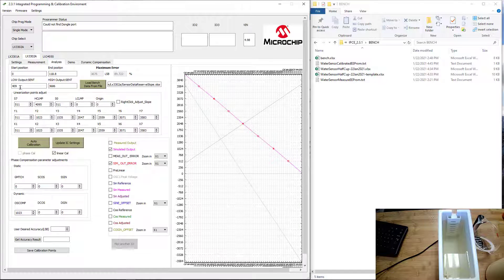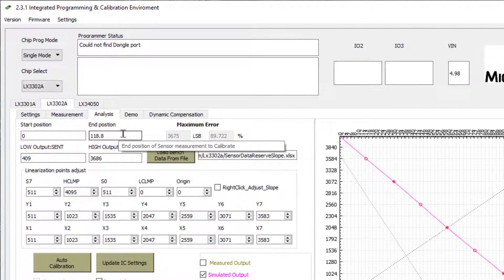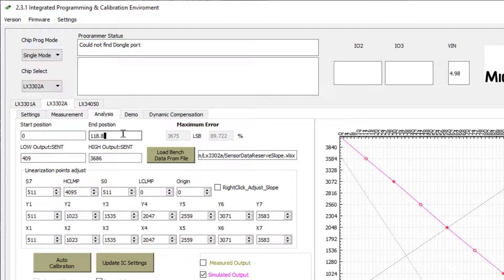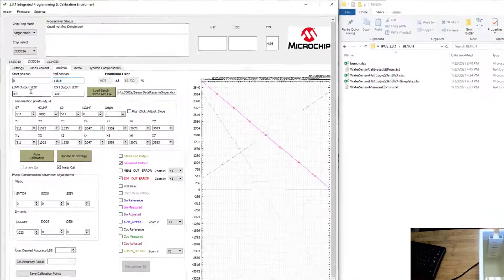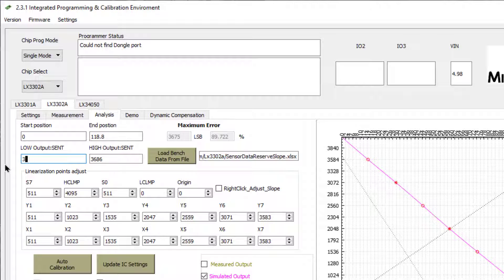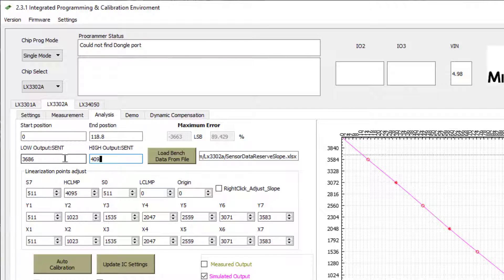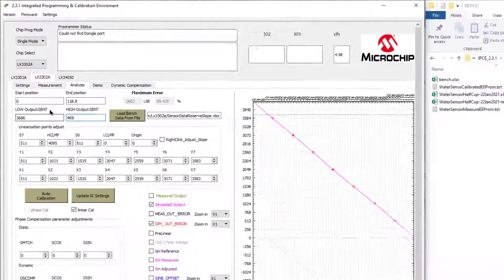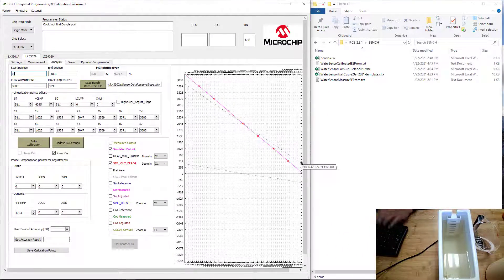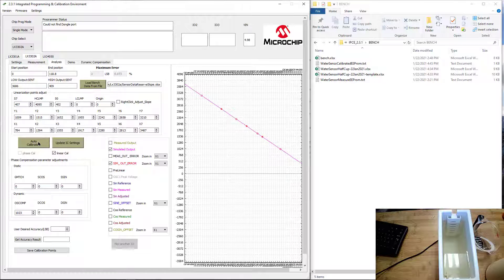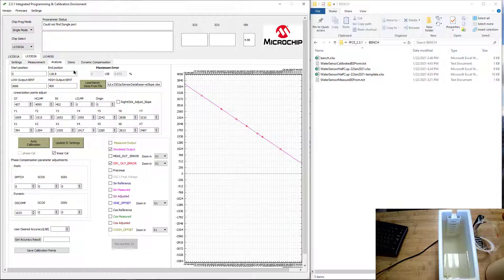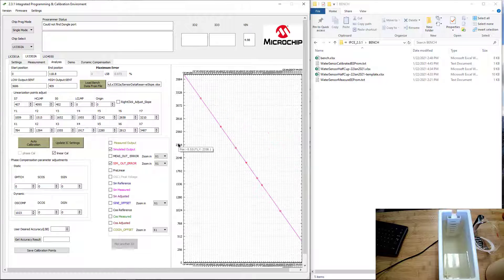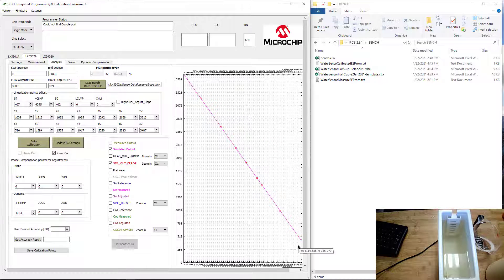In this case, what you're going to do is go from zero to the end value. This was collected data of 118.8 value. I don't know what type of sensor it was. Let's do 3686 as the high value, and then 409 as the low value. So now you've collected those. Now we have a negative slope as our guide, and now you can auto calibrate with that solution there. So that's how you reverse slopes using the IPC tool. If, when you collect your data, you want to collect it in that reverse slope condition.